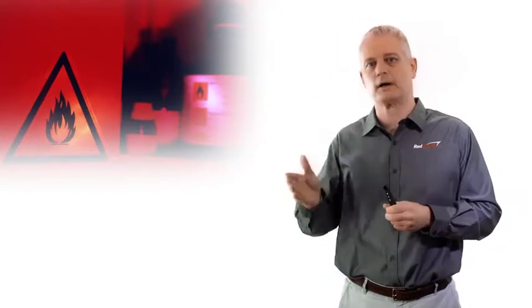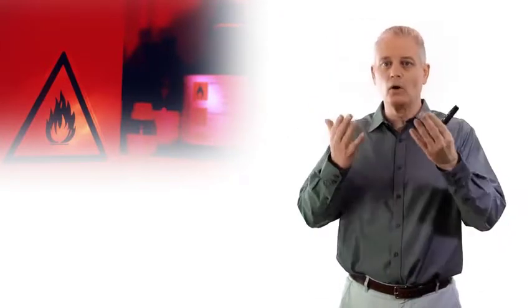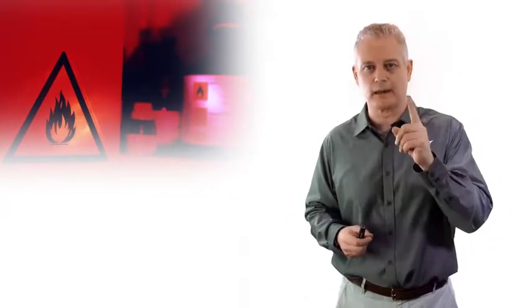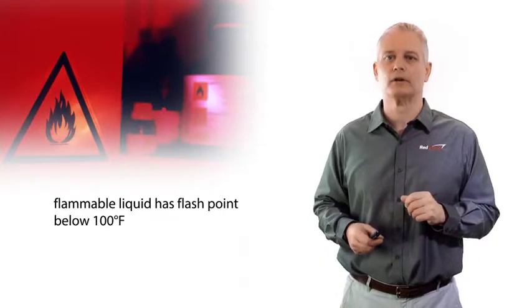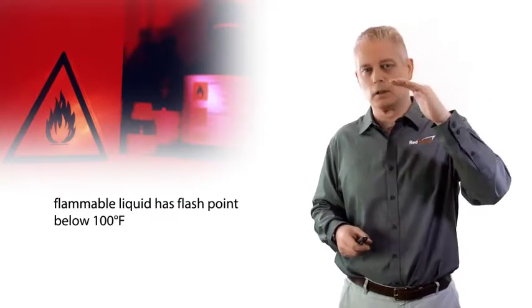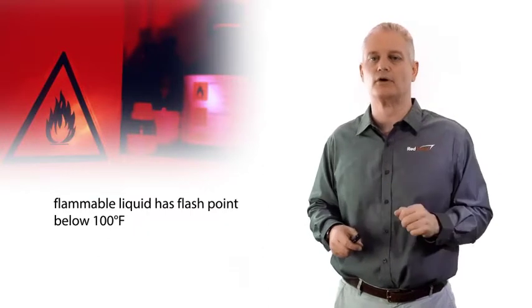The primary difference between a flammable liquid and a combustible liquid is they both will ignite, but let me give you an example. Gasoline is considered a flammable liquid. A flammable liquid has a flashpoint below 100 degrees Fahrenheit by NFPA 30.